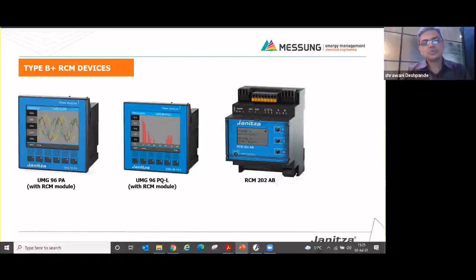Now it is very difficult for us to take you through all the Janitza devices in this webinar. For that, we will focus only on the main RCM device, that is the RCM 202 AB. The 202AB can identify all three types of RCM problems, that is A, B, and B+. It has a Modbus interface, two digital outputs, two analog outputs, and it can also identify harmonics up to 20 kilohertz.